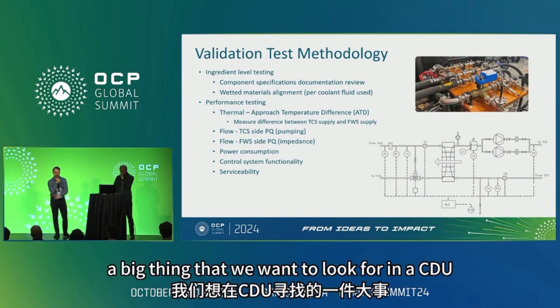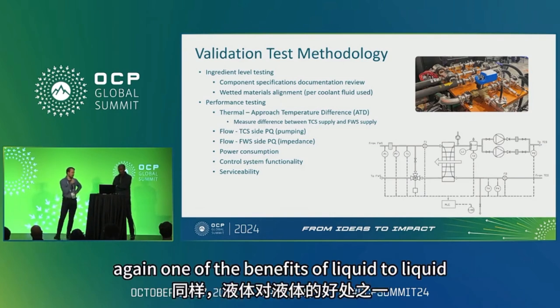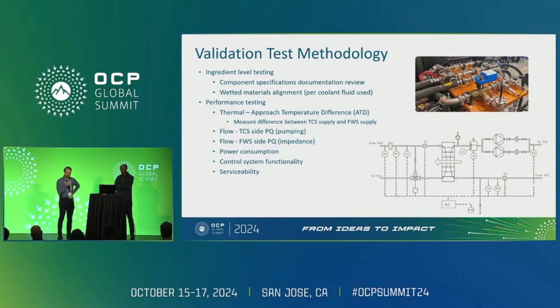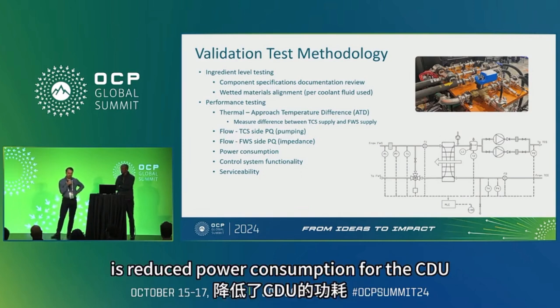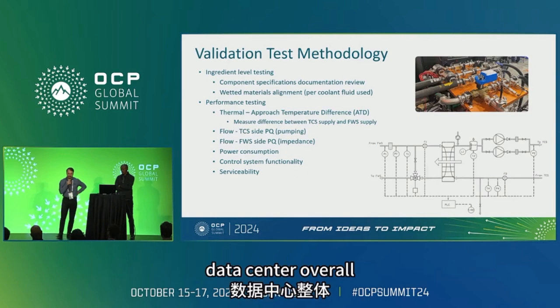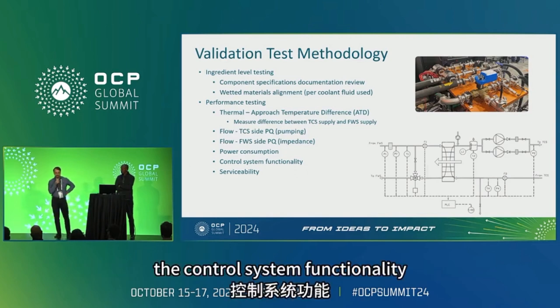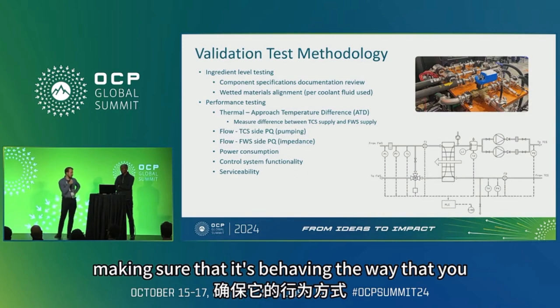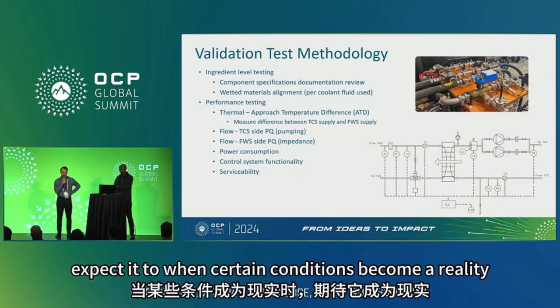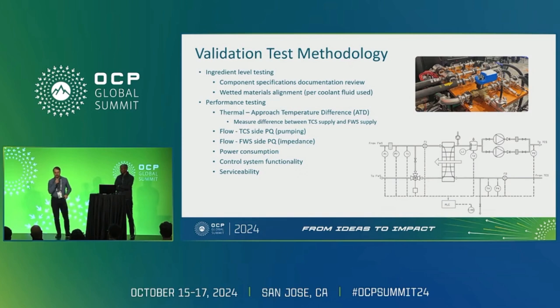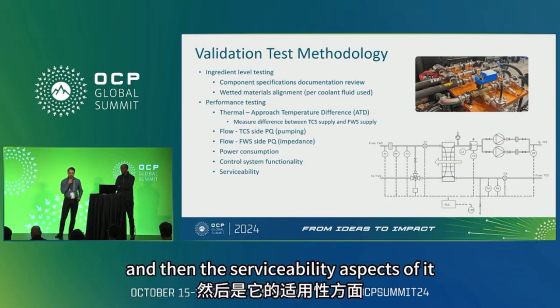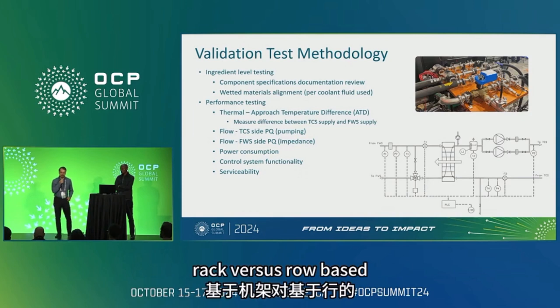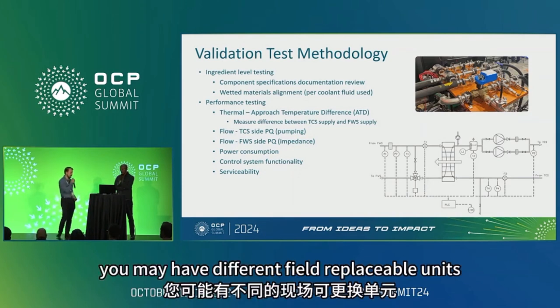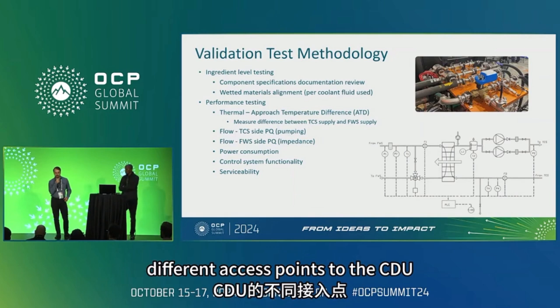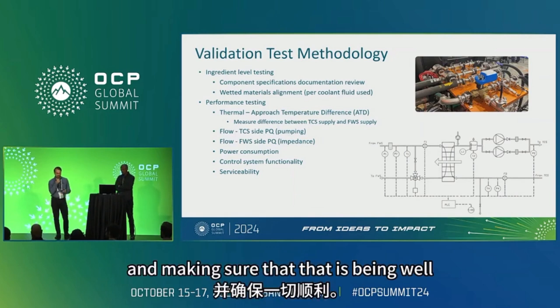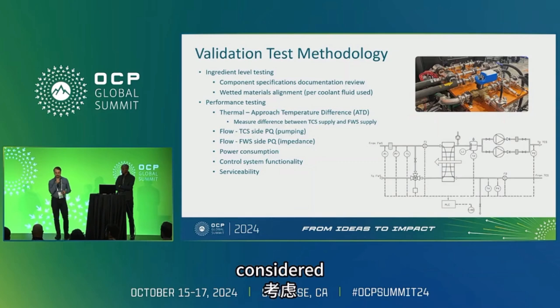Power consumption is a big thing that we want to look for in a CDU. Again, one of the benefits of liquid to liquid is reduced power consumption for the CDU and reduced power consumption for the data center overall. The control system functionality, making sure that it's behaving the way that you expect it to. When certain conditions become a reality, how will it react? And then the serviceability aspects of it. Rack versus row-based, you may have different field replaceable units, different access points to the CDU, and making sure that that is being well considered.